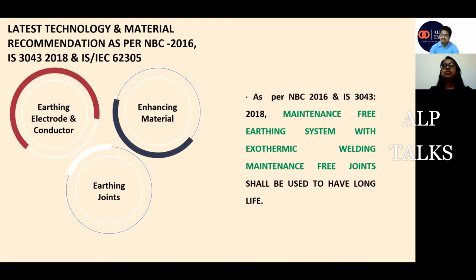See, the latest material or earthing conductor which is used now in the market is copper bonded steel rods. Yes, basically these are solid rods. If I tell you from the initial stage, firstly we were using plate earthings, but they require a larger area to install. We were using 300 by 300 by 3 mm plates of copper. So they are costly also, and they require a larger pit size too. After that, we moved to pipe earthing, where we were using copper pipes and GI pipe earthing. They also have their own disadvantages, as using a hollow pipe decreases the life of the earthing system.